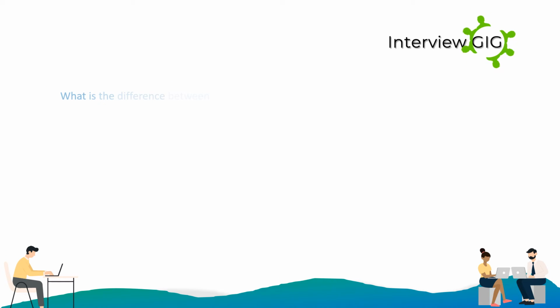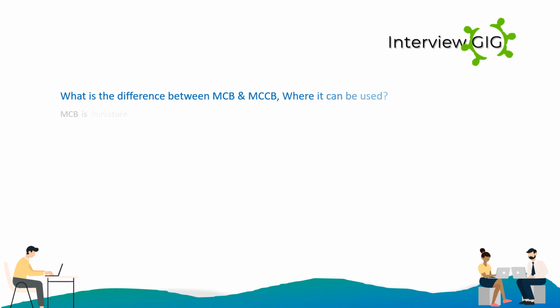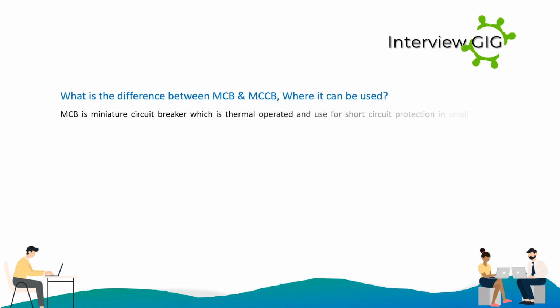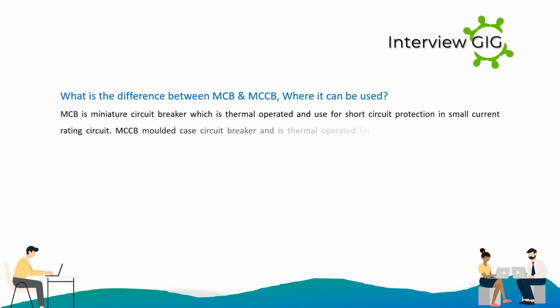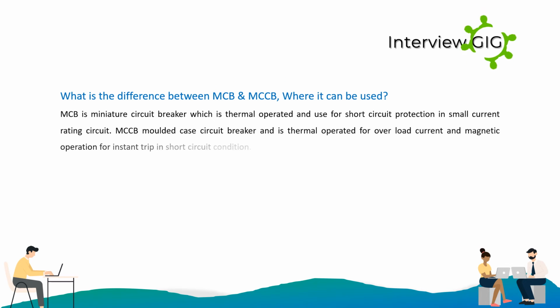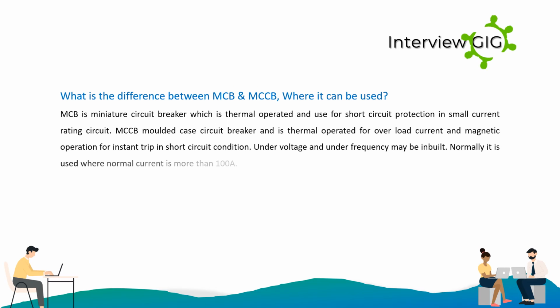What is the difference between MCB and MCCB, and where can they be used? MCB is a miniature circuit breaker, which is thermally operated and used for short circuit protection and small current rating circuits. MCCB is a molded case circuit breaker and is thermally operated for overload current and magnetically operated for instant trip in short circuit condition. Undervoltage and underfrequency protection may be inbuilt. Normally it is used where normal current is more than 100 A.